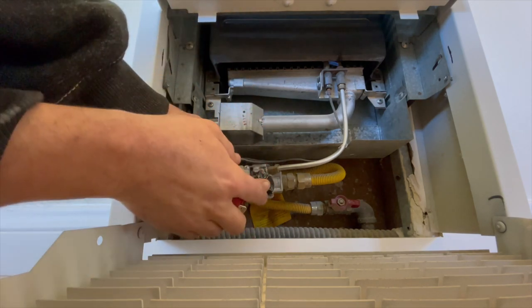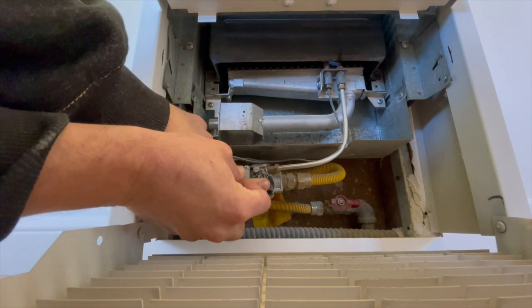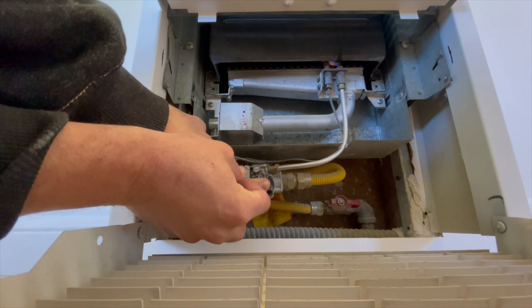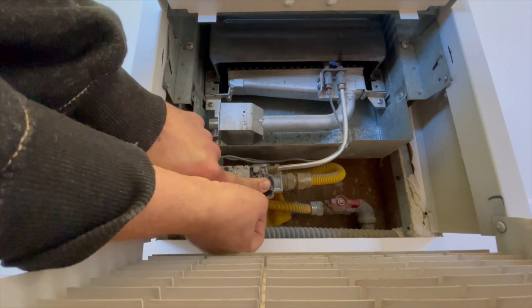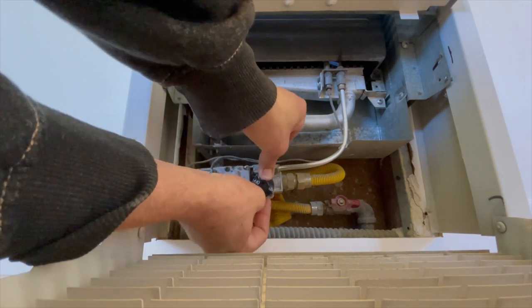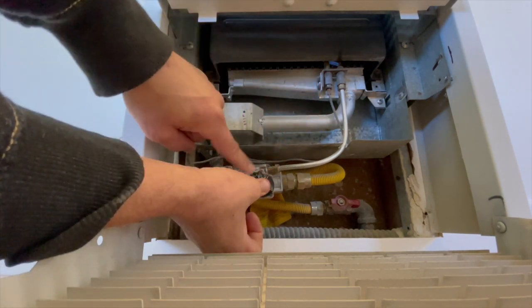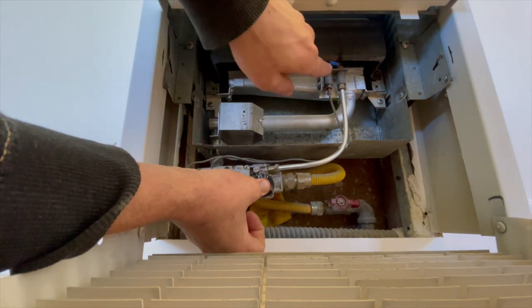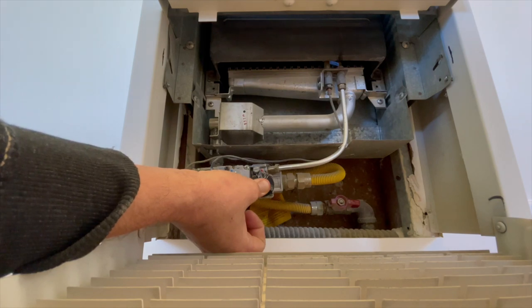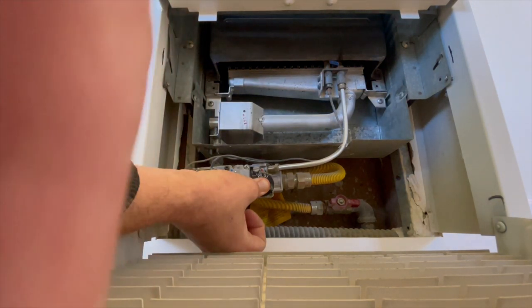I don't know if you can see it, but there is a blue light. That is the flame, and that is being held on with my finger. You cannot let this thing go. This is the most important part. You have to hold this thing down while that flame is still on. If that flame goes out, you're not holding it properly down or all the way, or you let it go too soon. So minimum 30 seconds. There's my flame.